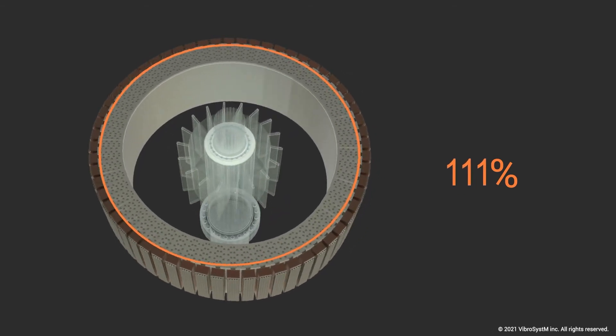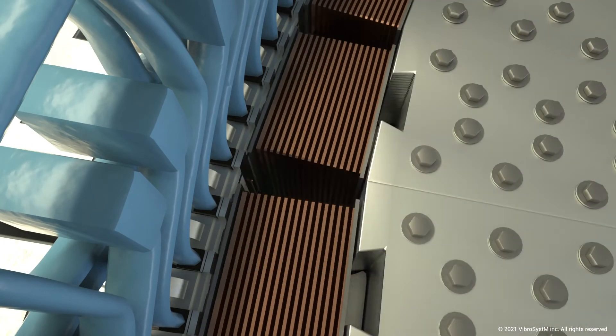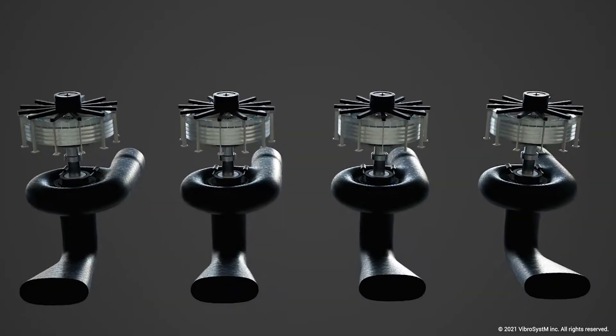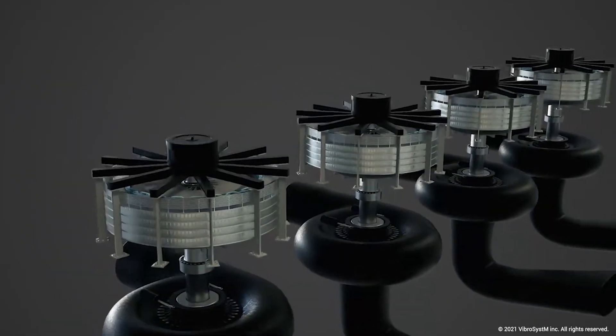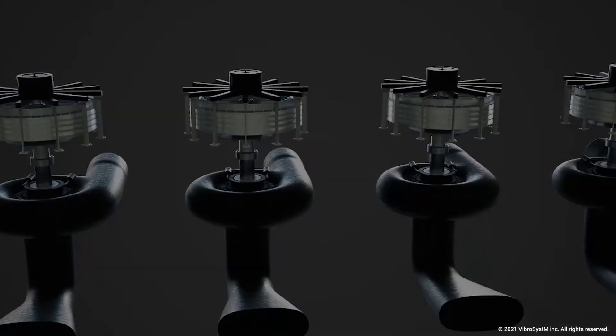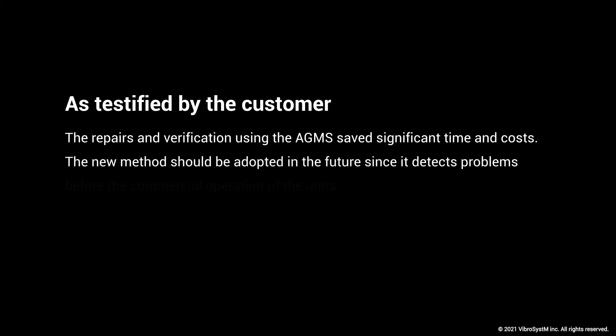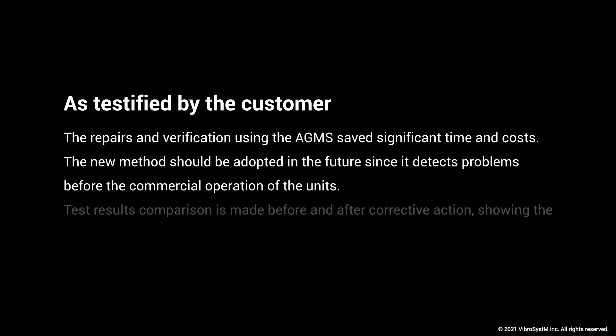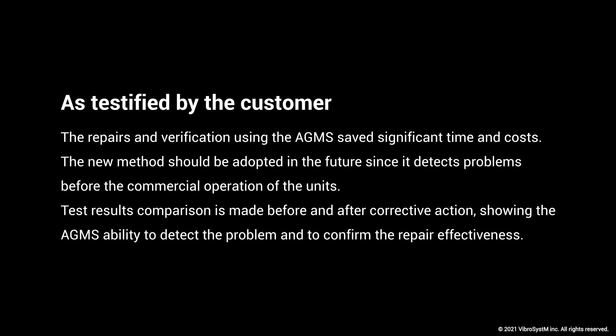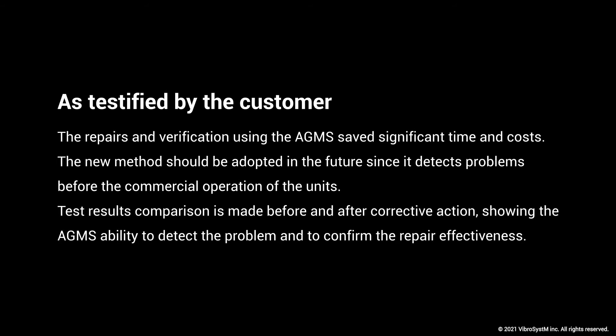Fortunately, the rotor performed flawlessly. Had that problem been left unchecked, the utility might have experienced four major rotor-stator rubs causing tremendous damage. VibroSystM's air gap monitoring system — commonly known as AGMS — helped the utility and OEM solve these issues and prevent any damage. As testified by the customer, the repairs and verification using the AGMS saved significant time and costs. The new method should be adopted in the future since it detects problems before commercial operation, and test result comparisons before and after corrective action confirmed the AGMS's ability to detect the problem and verify repair effectiveness.